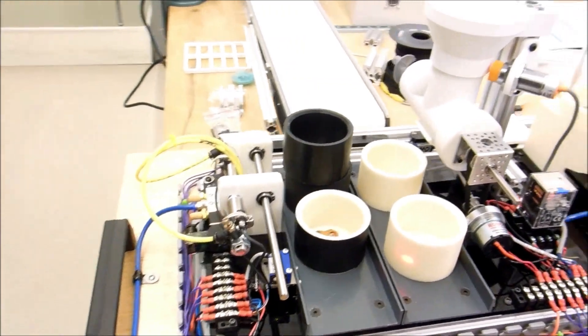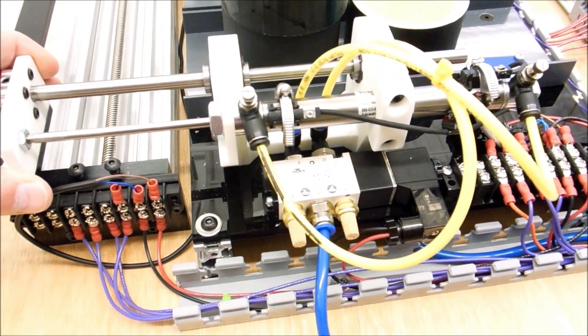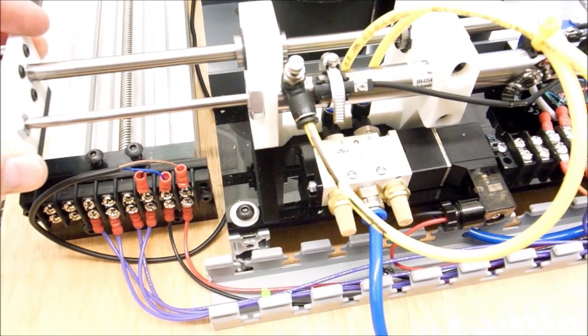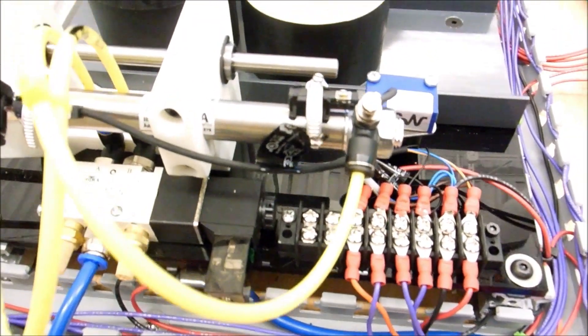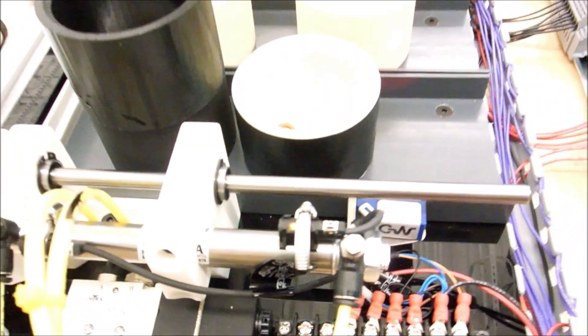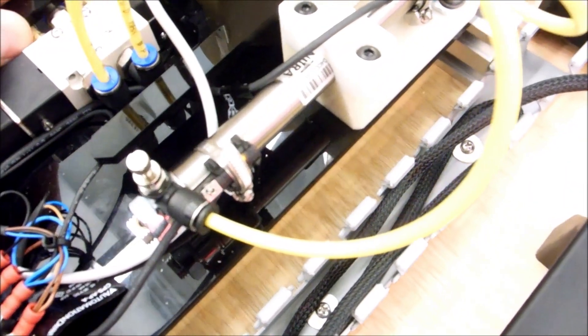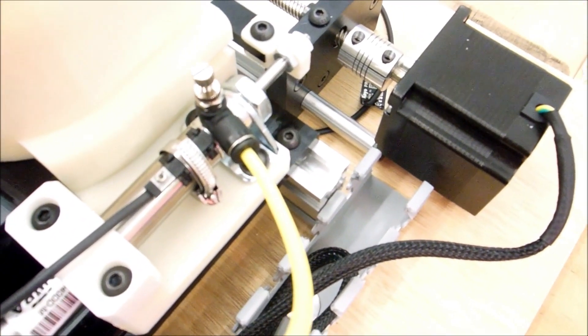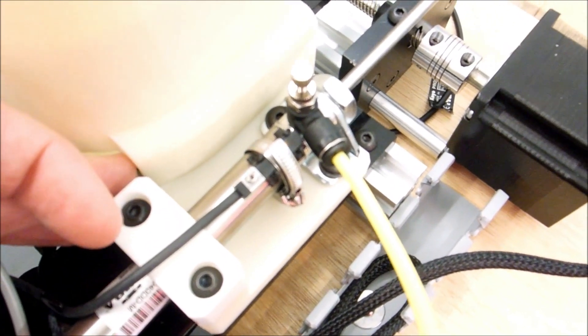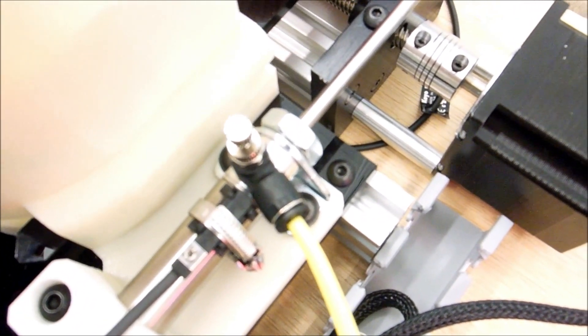So what we can do, and some of our sensors need to be adjusted, but the first thing we can do is we can go in here and we can manually move some of these sensors. And right here, hopefully we can see right there, is an LED that shows when we're extended. So it's on and there it goes off. So we can make sure that that sensor is wired correctly. And then at the other end, we have another one for when it's fully retracted. So there it's fully retracted and the LED is on. There it's off. There it's on. And we're going to do the same thing for the other, the cup dispenser. So right now it's fully retracted and you can see the LED. When we move it, the LED goes out. And now as we fully extend it, you see that, and I got to get to the fully extended position, that the LED comes on. And there it goes off. There it goes back on. So we do get some indication that things are working.